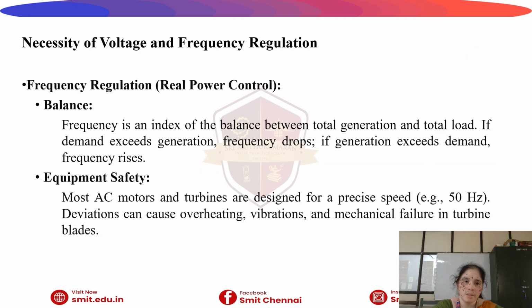The next topic is the necessity of voltage and frequency regulation. Before entering into this topic, we have to know the basic requirements of voltage and frequency regulation. Frequency is directly related to the real power, and if generation is not equal to load, the frequency changes. The basic principle in a power system is that power generation is equal to load. If the load increases, the generator slows down and the frequency decreases. And if the load decreases, the generator speeds up and the frequency increases. So the control of the frequency is obtained by real power control.